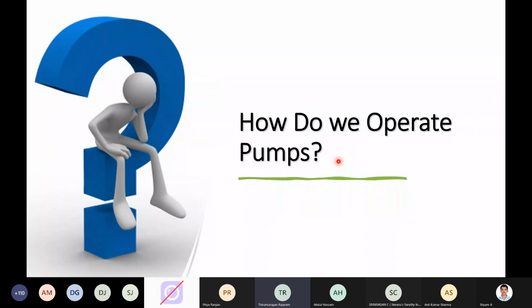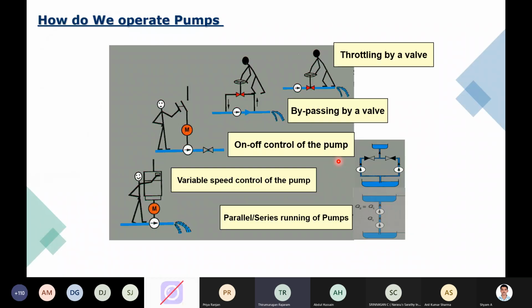We have just touched upon some of the layouts on other situations. Now we can see how the pump is being operated at its site conditions. What are the situations currently? You can see throttling by a valve. On the discharge side, you have a throttle valve, so people try to open or close it based upon the flow required.